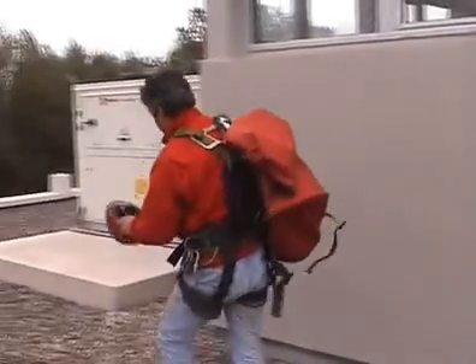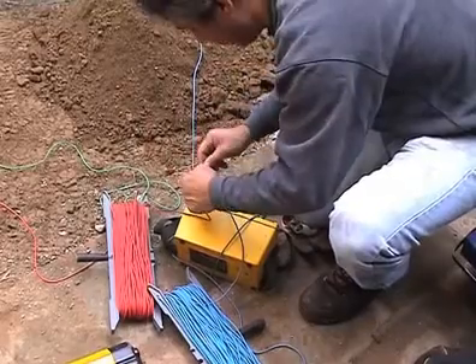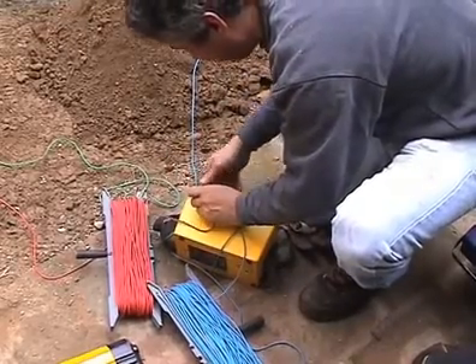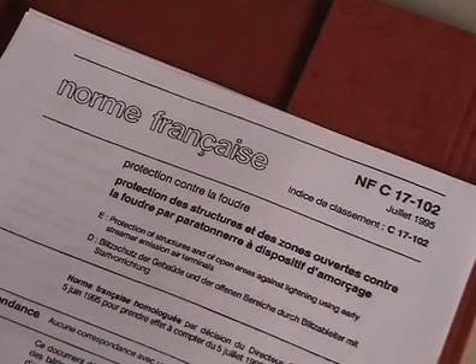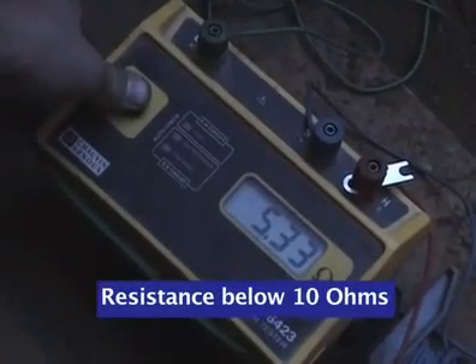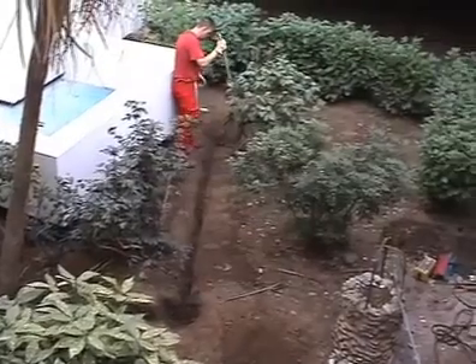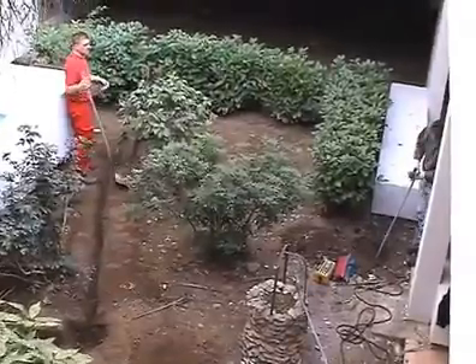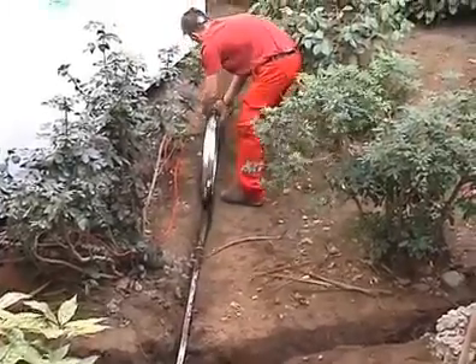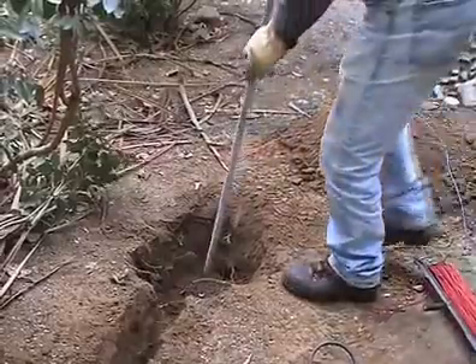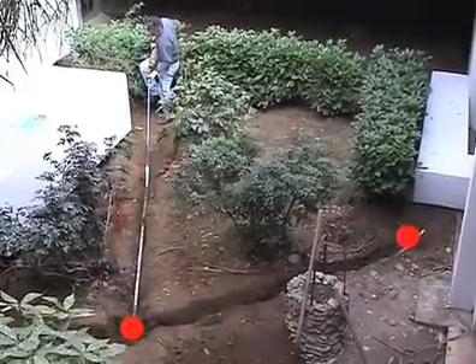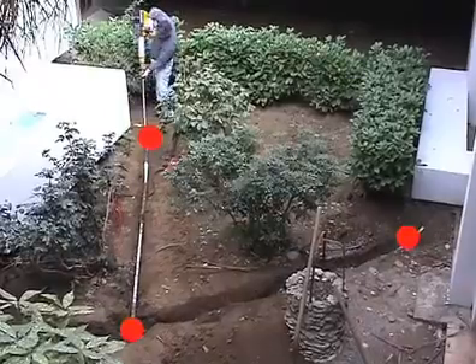Let's now follow a team of specialists that will show us the practical and informative aspects that have been applied to ensure a proper lightning installation and also to achieve a correct earthing system, knowing that this one has to be lower than 10 ohms. With regards to the small space allowed in this particular site, you will notice that the earthing system has a triangular shape. This earthing system will be made of tin-plated copper tape and 3 earth rods.